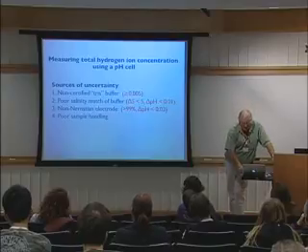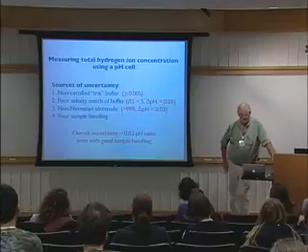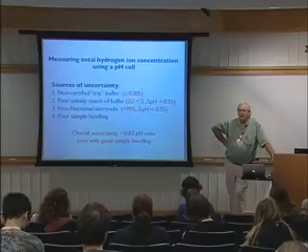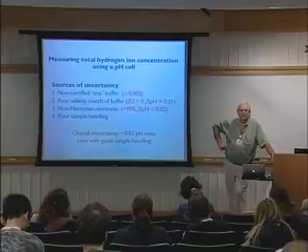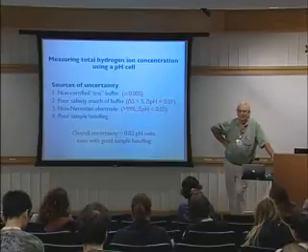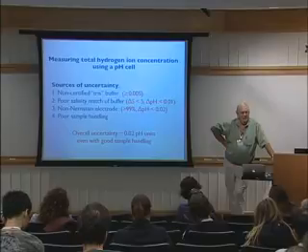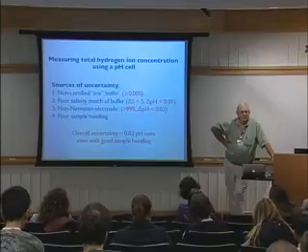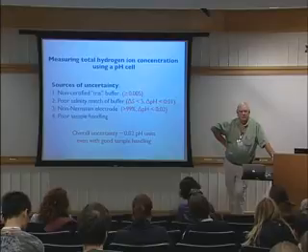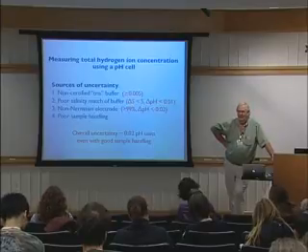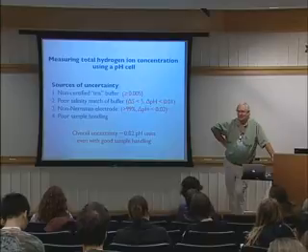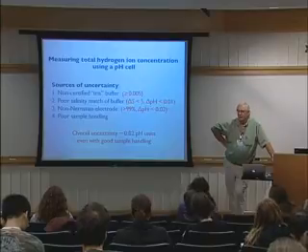I would say, if I was picking a number out of a hat, and it's a hat with a limited number of balls in it to select, the overall uncertainty of an electrometric pH unit is of the order of 0.02. You could squeeze it better than that. But the bad news with all of these things is if you want a factor of 10 improvement in anything, it's a factor of 100 extra work in most cases. So you might not really want to do that.